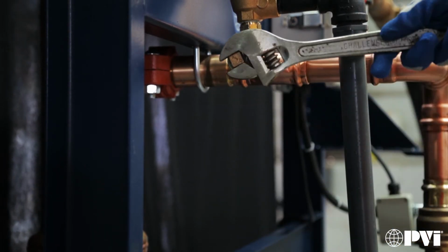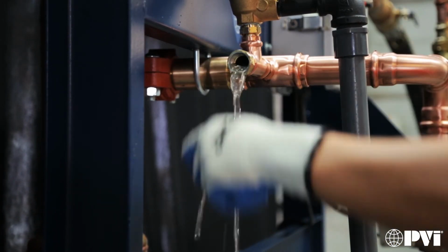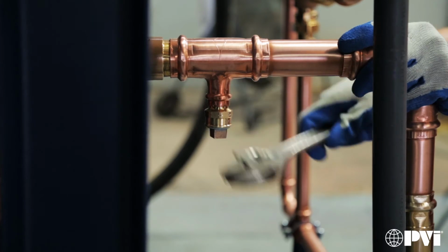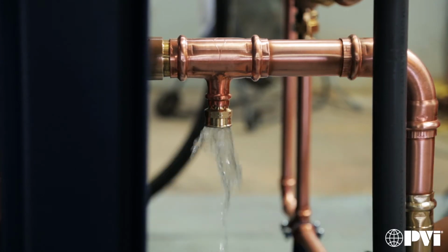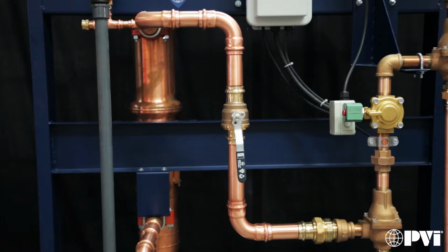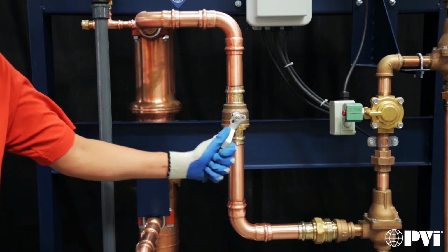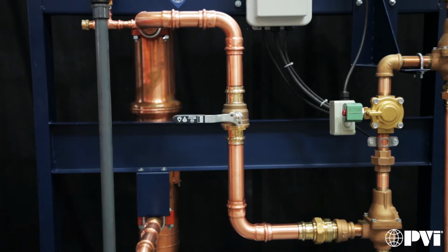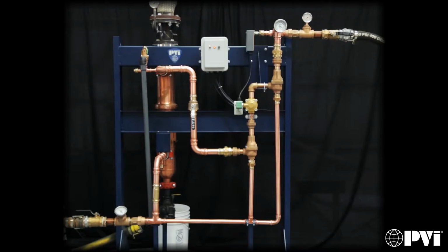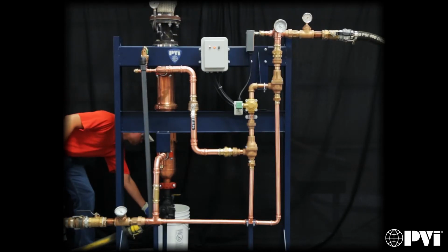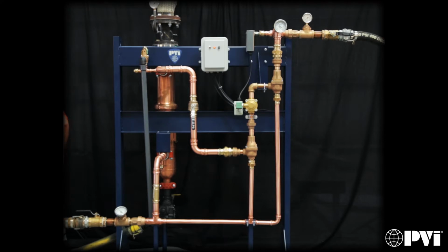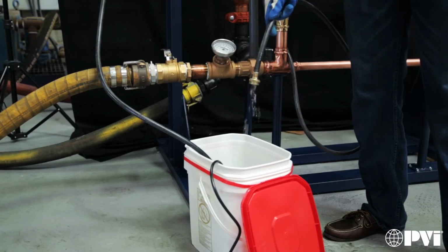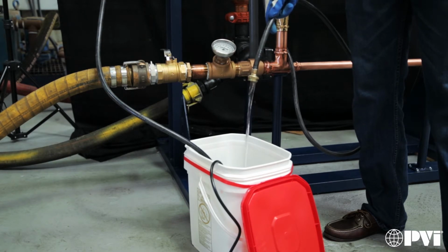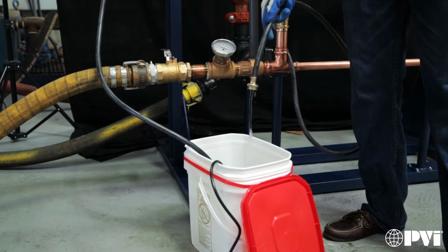Remove the clean-in-place fittings at the top and bottom of the water piping and set aside. The remaining water in the water heater, plumbing, and heat exchanger will drain from the unit. Close the isolation valve to prevent water from exiting the heat exchanger and entering the plumbing system. With the unit completely drained, empty the bucket and replace it under the lower clean-in-place fitting so the cleaning fluid will drain into the bucket. Have the technician put on all safety equipment, including chemical splash goggles and rubber gloves. Then fill the bucket with 2 gallons of heat exchanger cleaning solution.